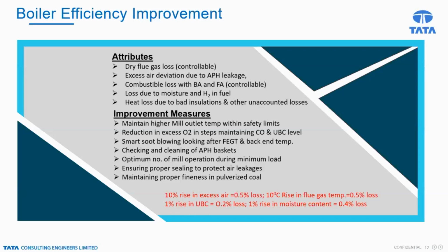Then there is heat loss due to moisture and also hydrogen in fuel, because hydrogen is converted into H2O, which also consumes the latent heat of evaporation. Because of that, the boiler efficiency would be low. Then there is heat loss due to radiation, insulation and unaccounted losses. So we know the factors that affect the boiler efficiency. If you take care of those, the boiler efficiency would be equal to its design value, and we will have a better plant heat rate.